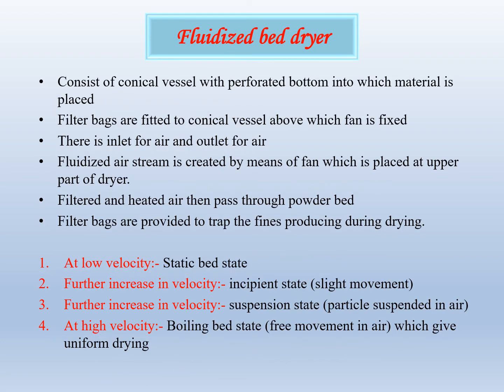Next we will see the fluidized bed dryer. It consists of a conical vessel with a perforated bottom into which material is placed. Filter bags are fitted to the conical vessel above which a fan is fixed. There is an inlet for air and an outlet for air. A fluidized air stream is created by means of a fan which is placed at the upper part of the dryer. Filtered and heated air then passes through the powder bed. Filter bags are provided to trap the fines produced during the drying.